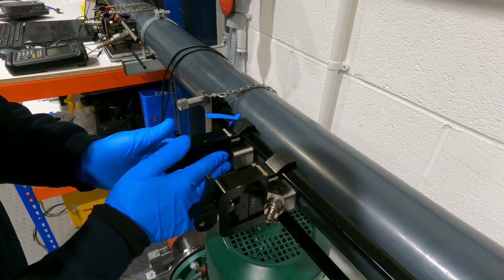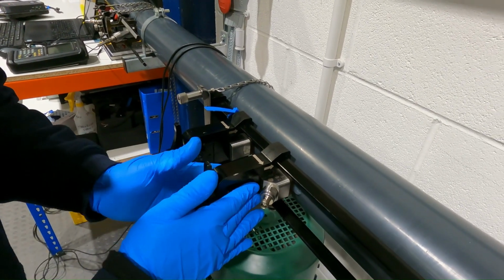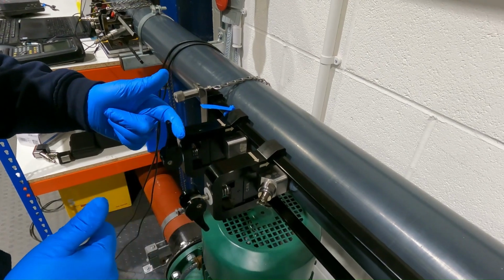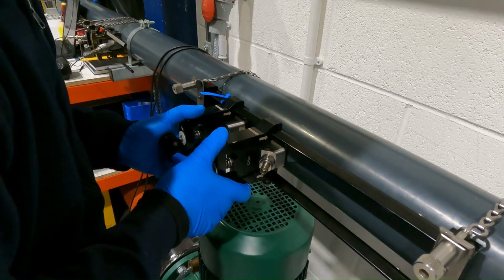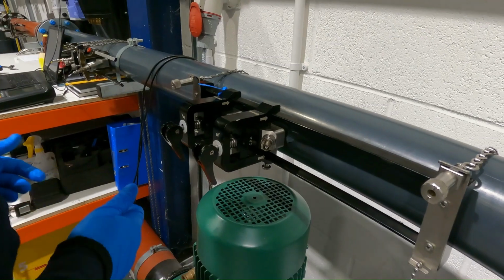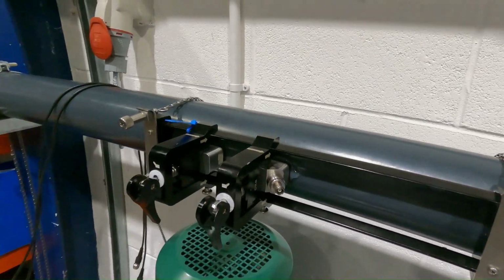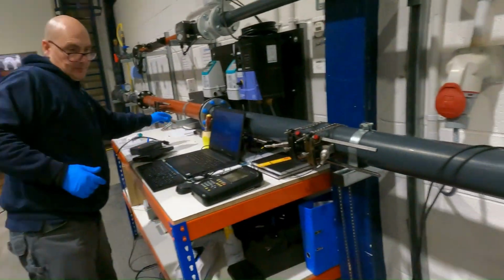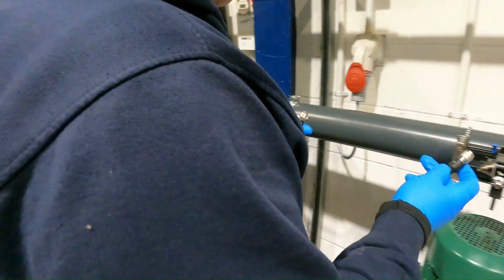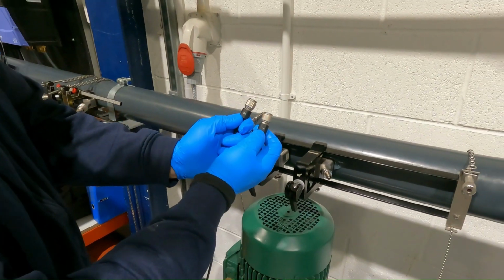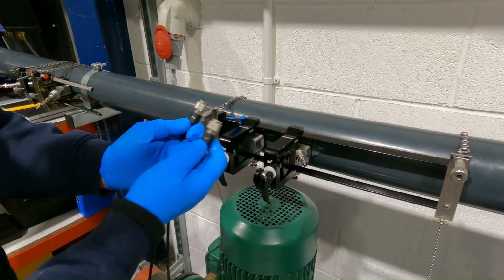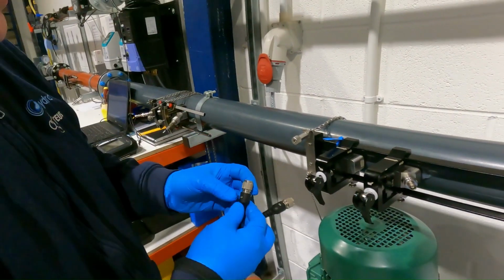Okay, once we're happy it's in the right place, we can put the clamps on, the spring will hold it against the pipe, and now we can attach the wire. So the XDR cable, you have upstream and downstream. Today the upstream's coming from the left.